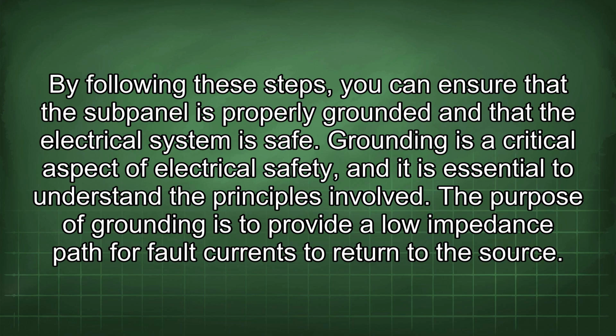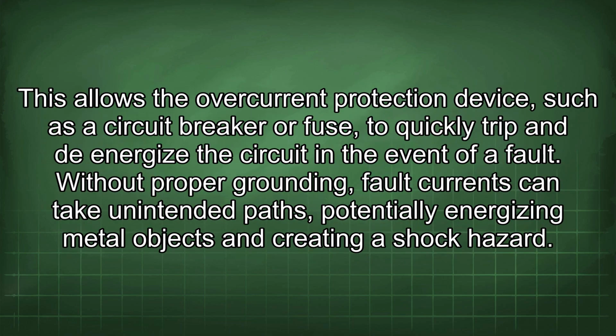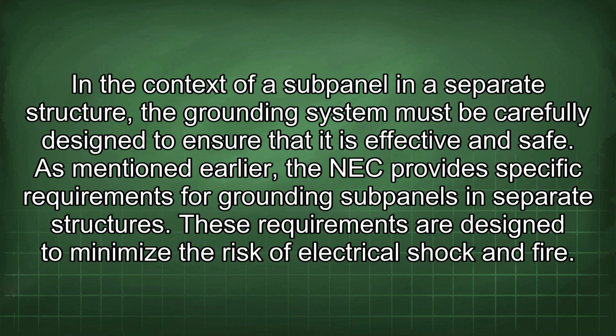Grounding is a critical aspect of electrical safety, and it is essential to understand the principles involved. The purpose of grounding is to provide a low impedance path for fault currents to return to the source. This allows the overcurrent protection device, such as a circuit breaker or fuse, to quickly trip and de-energize the circuit in the event of a fault. Without proper grounding, fault currents can take unintended paths, potentially energizing metal objects and creating a shock hazard. In the context of a subpanel in a separate structure, the grounding system must be carefully designed to ensure that it is effective and safe.